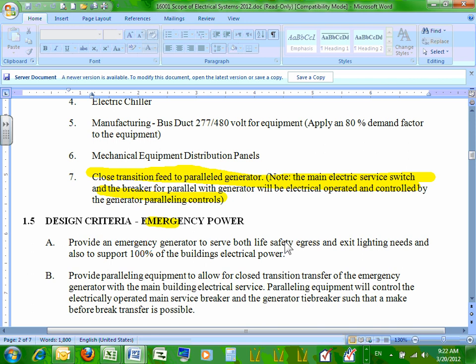Utility fails, the gear senses utility failure, it opens up this breaker, starts up the genset, where the genset comes up to voltage and sine wave, it closes the breaker, and everything comes back. But what I'm asking for is a closed transition transfer. Let's say there's a reason that we need to do some maintenance on this breaker. So I can go up to my controls on a closed transition and say make a closed transition transfer on the generator, because I need to have access to this breaker.